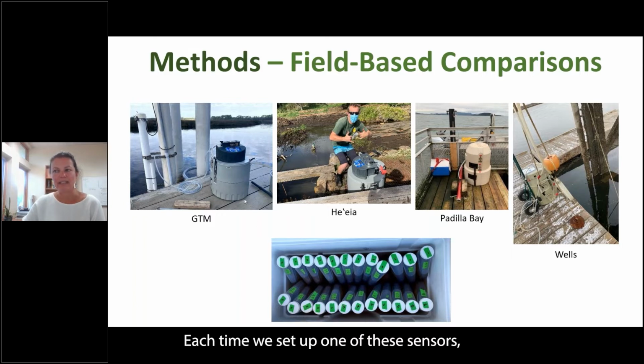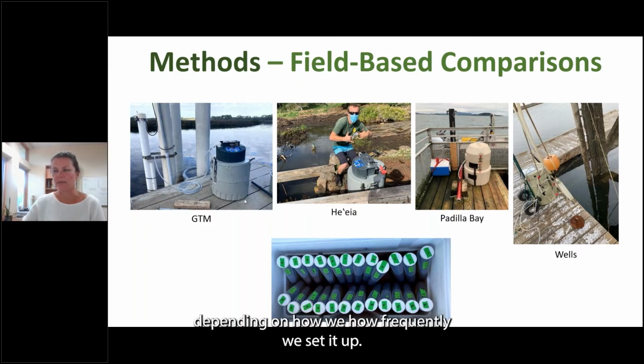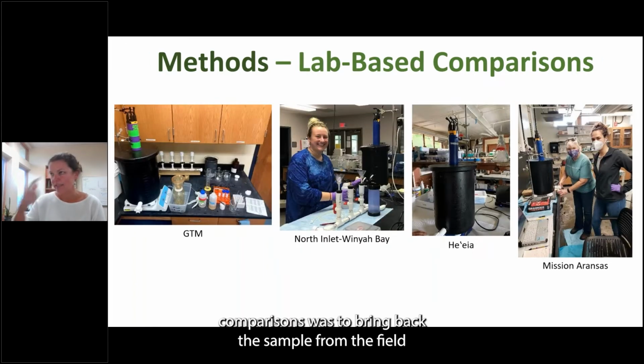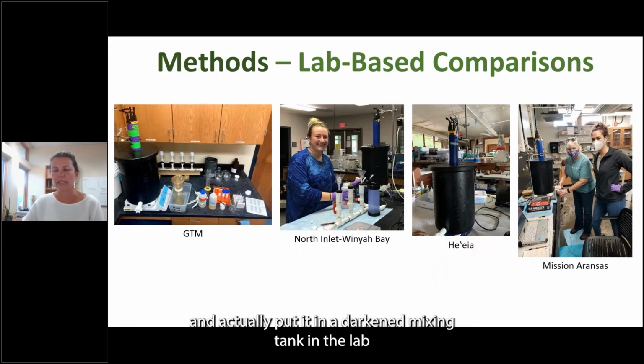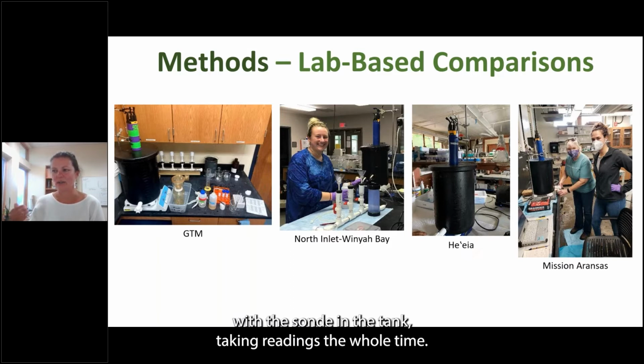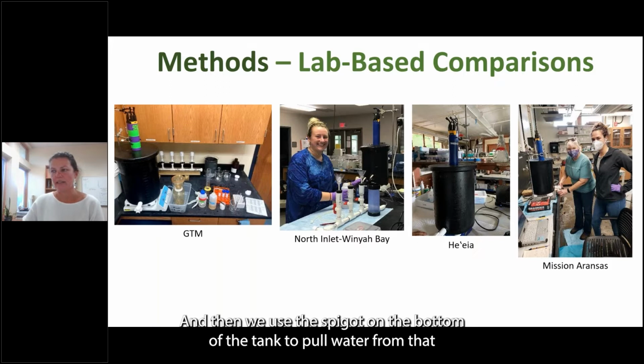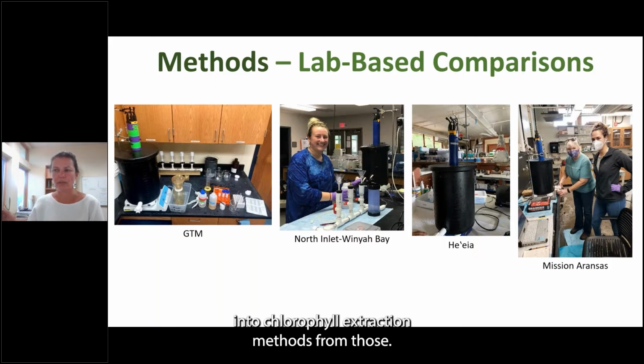Each time we set up one of these sensors, we got a number of samples depending on how frequently we set it up, but anywhere from 11 to 24 samples at a time over a tidal cycle. And the other way we did comparisons was to bring back the sample from the field and actually put it in a darkened mixing tank in the lab with the sonde in the tank, taking readings the whole time. And then we used the spigot on the bottom of the tank to pull water from that and do chlorophyll extraction methods from those. So this was a much more controlled way to do the comparison.